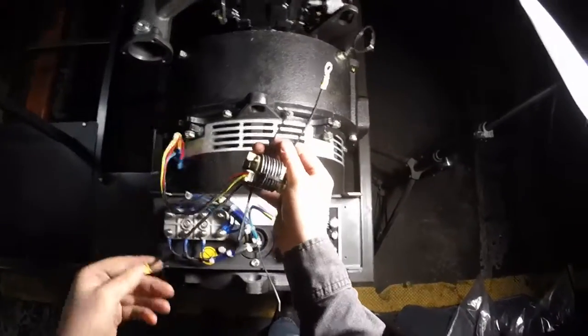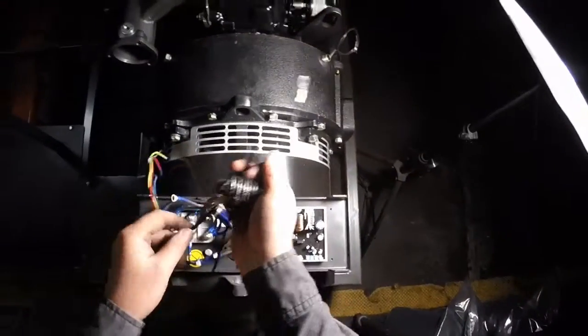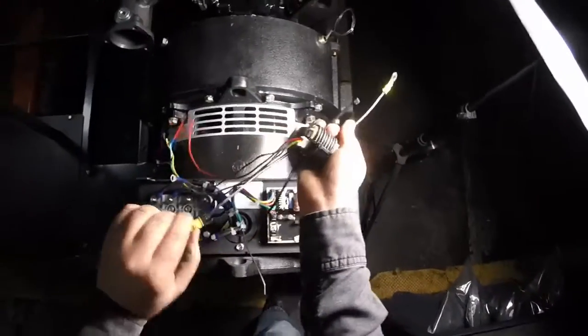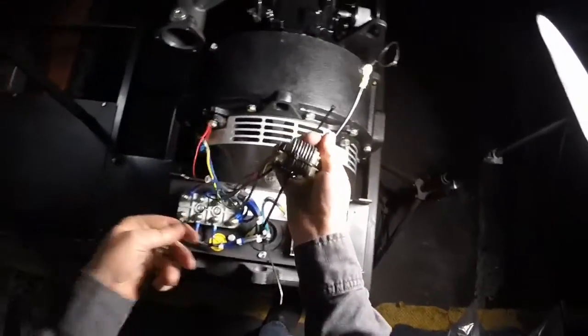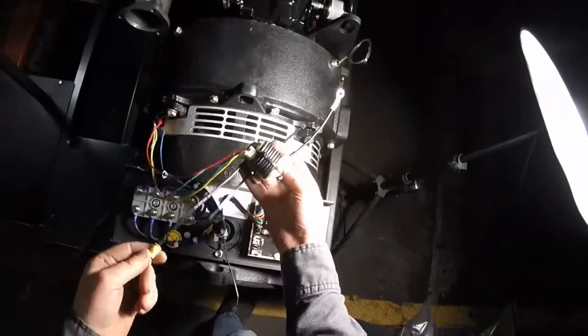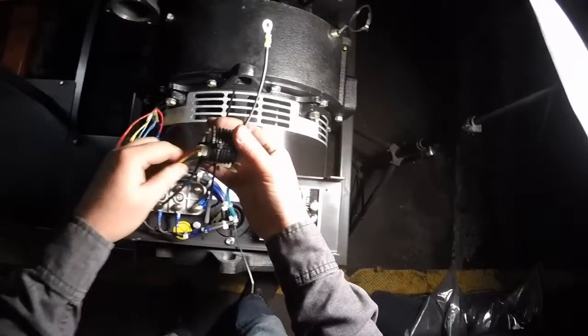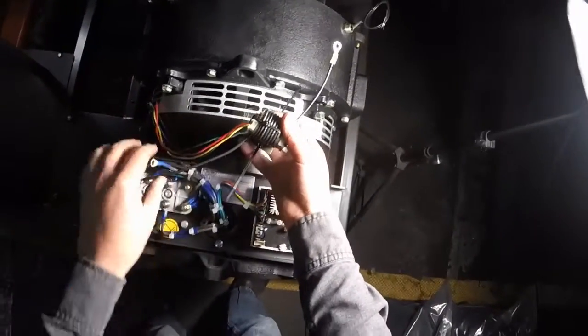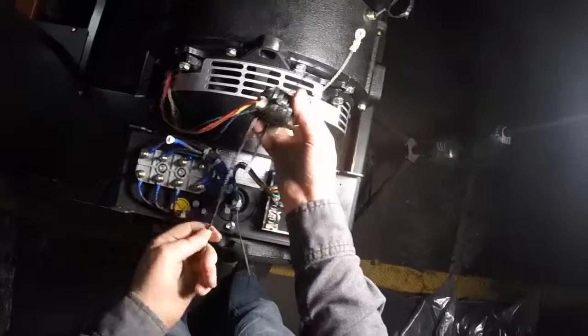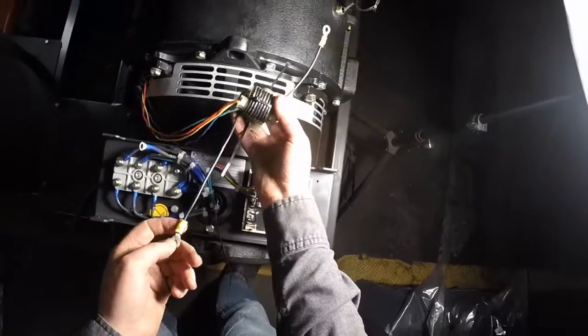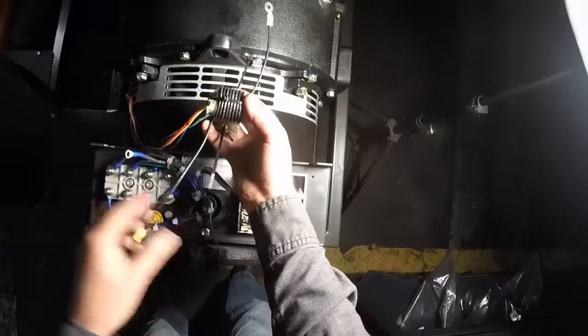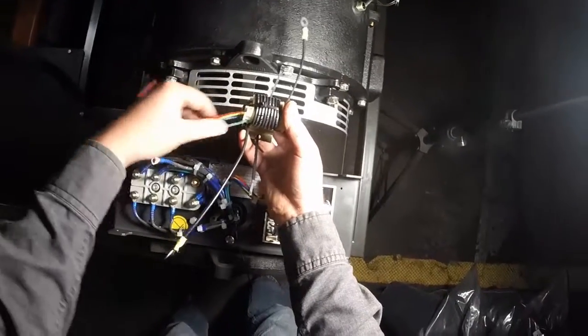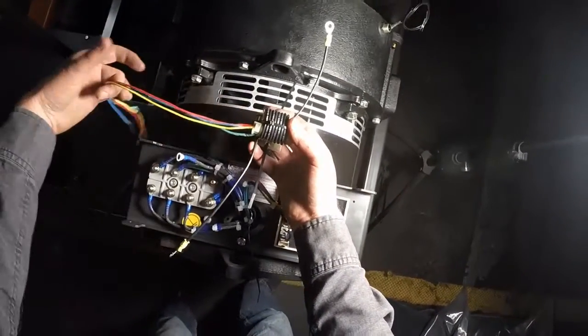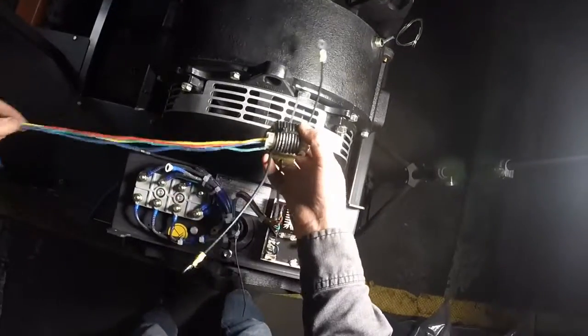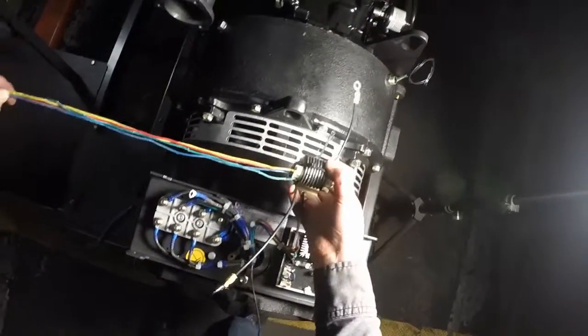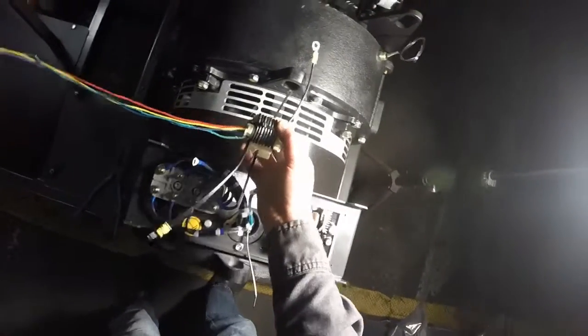One of the things that's important on the transformer is, like we experience on the these CTs, current transformers, the polarity of them is important. And so I'm wanting to keep the geometry of this consistent. So in this case, we are going to connect from the wire that is going into the terminal, or into the coil, with the wires facing to the left side.